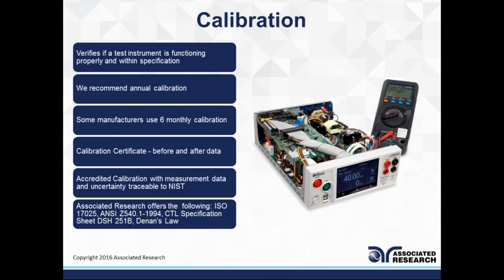Then, the other thing the auditor will ask you for is data or proof of calibration. That comes with calibration certificates, before and after data of your instruments, and accredited calibration with measurement data and uncertainty, traceable to NIST. All these services are available, and the data sheets for calibration provide all the data points, and the auditor can look at them and see that all those different areas of an instrument were calibrated to the standard, are meeting the standard, and pass the calibration.